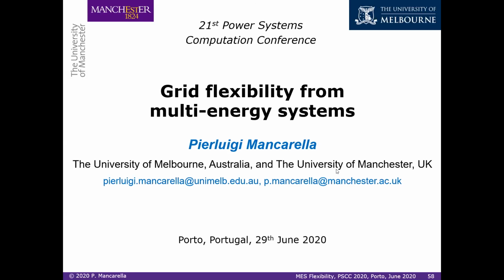Are all these points admissible? No. Actually, the flexibility operating region would change depending on the network constraints and the operating point. I skipped one of the slides, but there are also some interesting examples where you show that these regions may also be non-convex, the moment that you have integer constraints like switching generators on and off, for example. So these flexibility regions change with time, and with time you also have network constraints that change. So it becomes really an interesting problem.